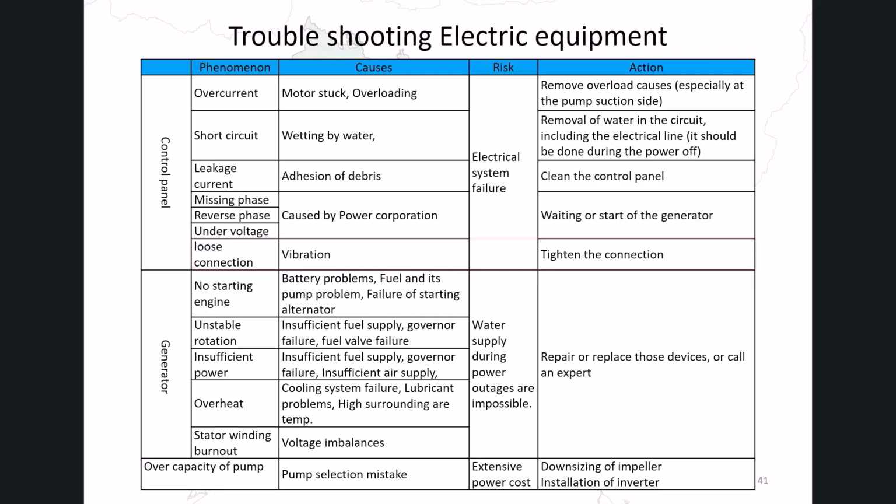For example, if you observe loose wiring connection at the control panel, it could be caused by vibration. And the troubleshooting table guides you for the necessary action to take. In this case, you have to tighten the parts, bolts, nuts and organize wiring. This is how what we learned in the confirmation points and necessary actions can be quickly applied by referring to the troubleshooting table.